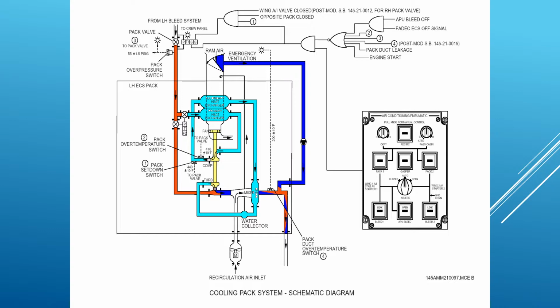So there's a set down switch. It's set to a lower temperature. It's set to 221 degrees C. What that will do is send an electrical signal to the pack valve, and it resets it to the normal flow mode. Hopefully that will take the heat off, excuse the pun, the air cycle machine, and it won't overheat and trip.